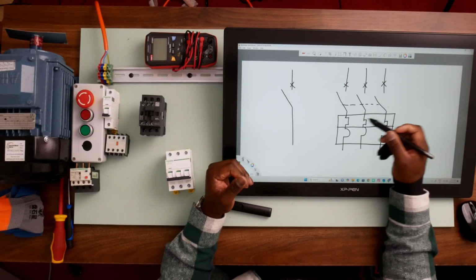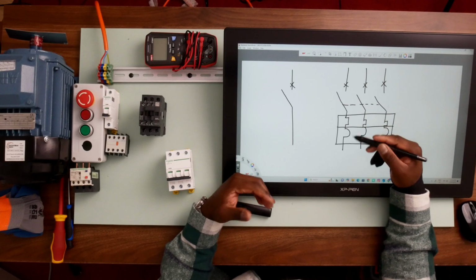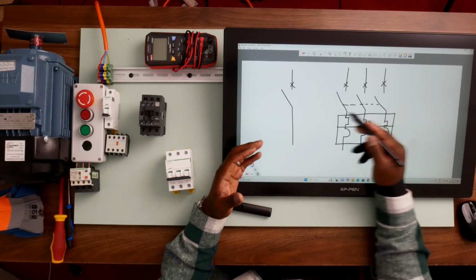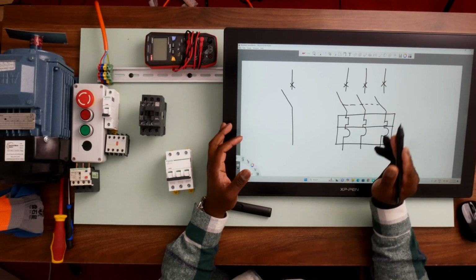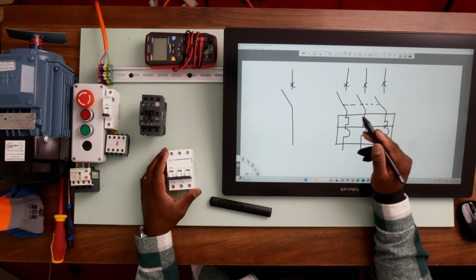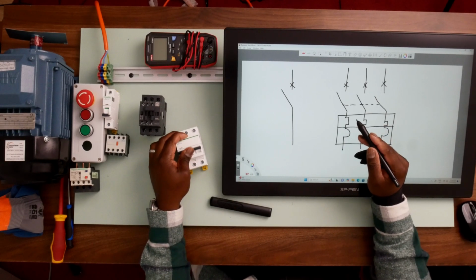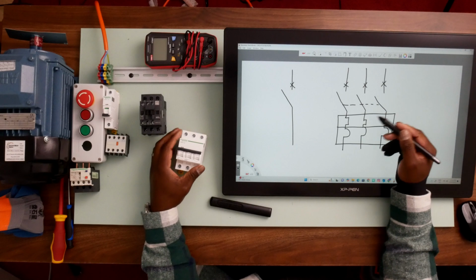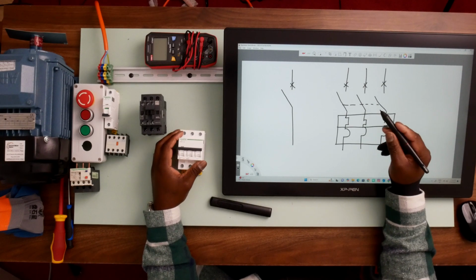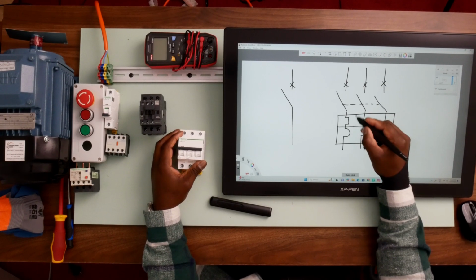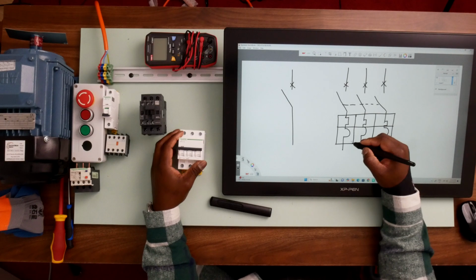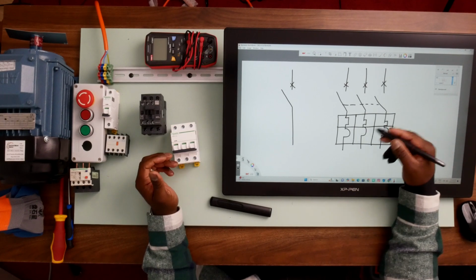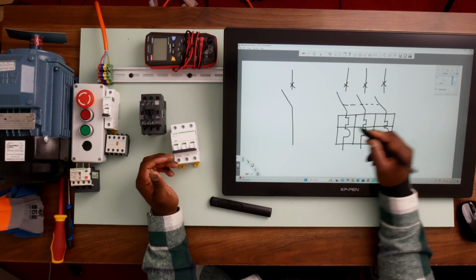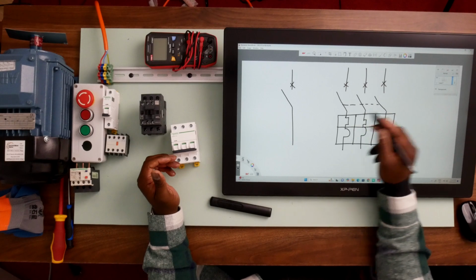Because what could happen is a short circuit could occur in one phase. If they were not mechanically linked like this, only that phase would trip. But since we've linked them like this, if a short circuit occurs in just one phase of this circuit breaker, then that phase tripping is going to force the other two phases to trip as well.